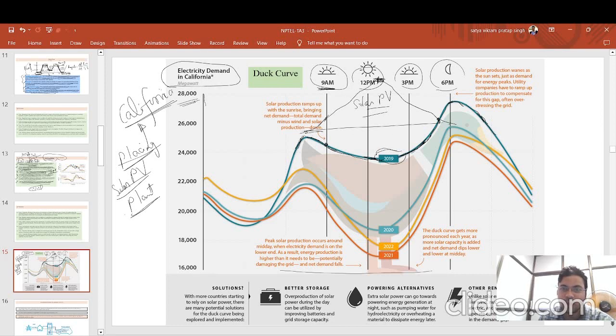So this curve shows that if you increase this PV generation at a huge level, the demand from the grid lowers down. So what happens then? In that time frame when demand from these power plants is very low, what are the two options? You can reduce generation from these power plants, or you can stop the power generation. But we cannot stop the power generation, because you need a certain time to again start this power plant. So you need a sudden ramp rate.